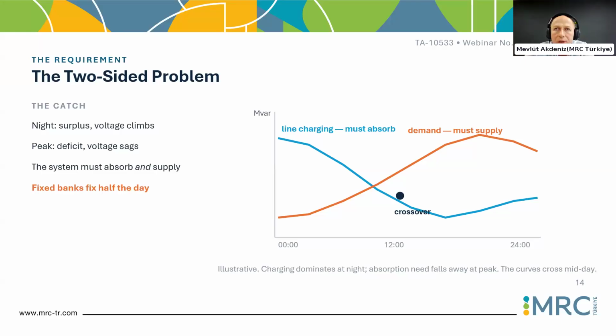and if you don't have any reactive support from the PV, called Q at night, let's say, because the PV plants are not operating during the night, if there is no load, we cannot de-energize this line, causing surplus reactive power, because de-energizing the line solves the excess reactive power, but it also separates, islands, the PV plants from the grid.